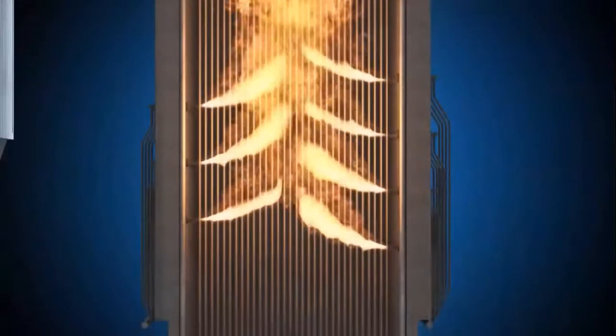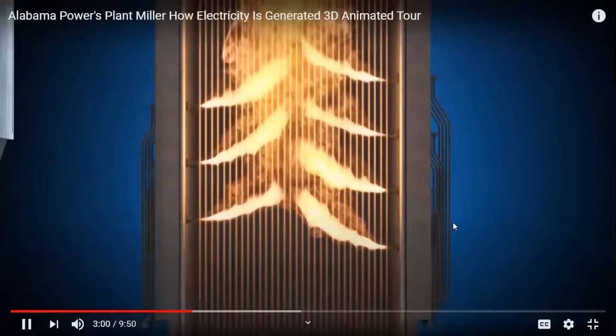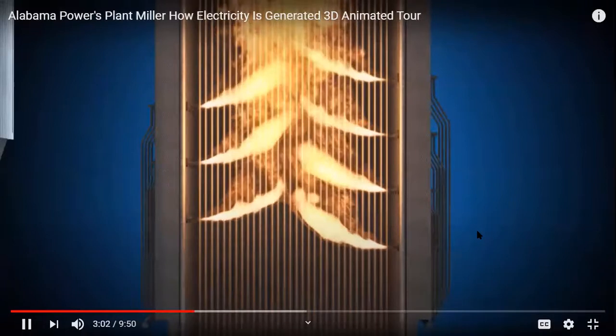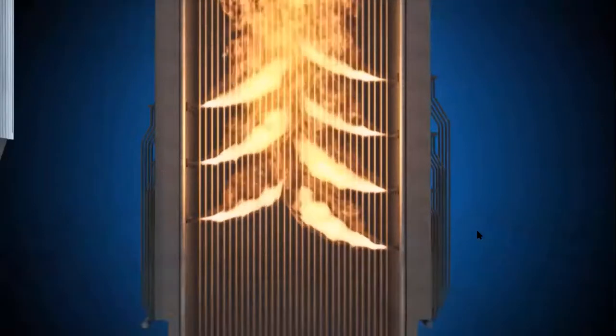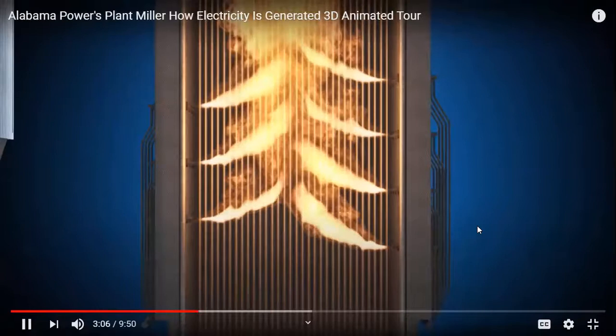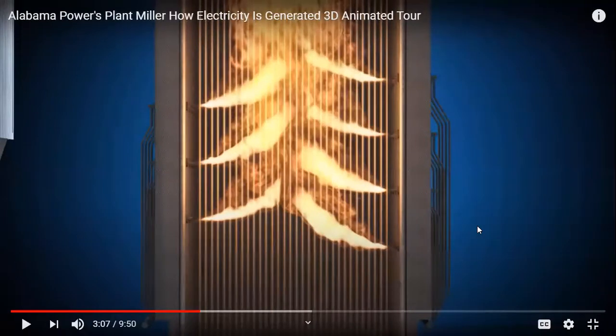When the particles of coal reach the burners, they are mixed with secondary air that has been preheated to over 500 degrees to support complete combustion inside the boiler. So you see that when we combust coal, we don't directly combust chunks of coal, right? We first grind it into tiny powder, then we're generating particles into the boiler, because in that way the combustion will be more complete.